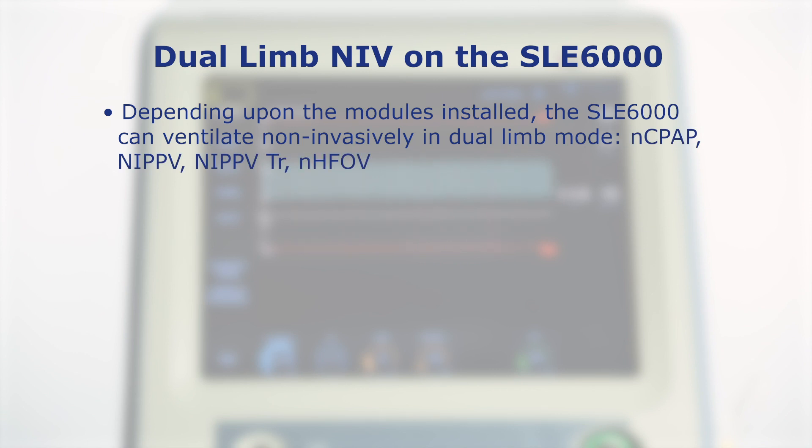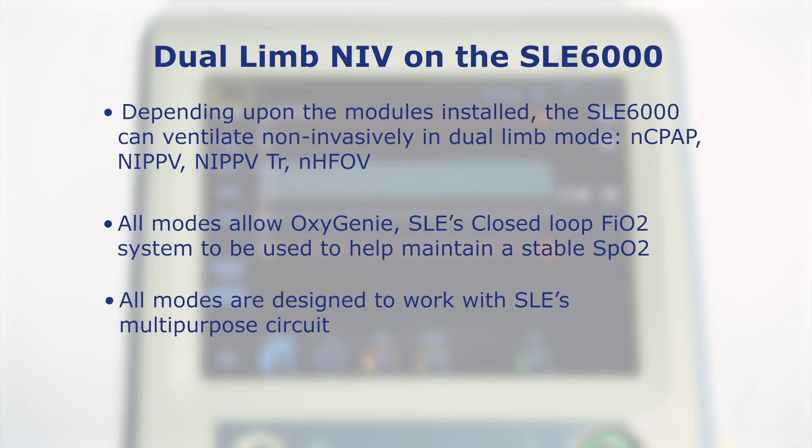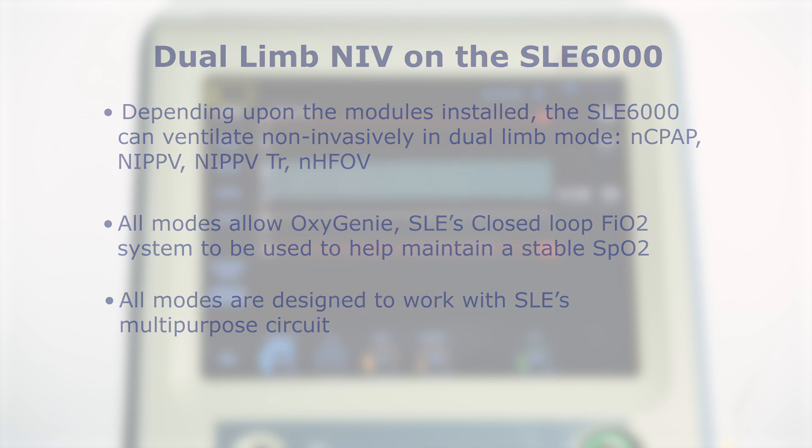Depending upon the modules installed, the SLE6000 can ventilate non-invasively in dual limb mode: NCPAP, NIPPV, NIPPV triggered, and NHFOV. All modes allow OxyGenie, SLE's closed-loop FiO2 system, to be used to help maintain a stable SpO2. All modes are designed to work with SLE's multi-purpose circuit.